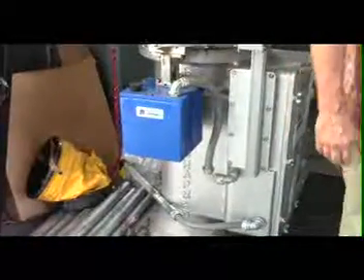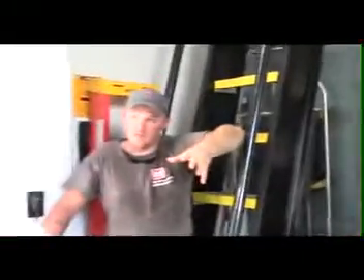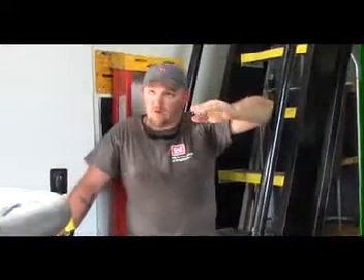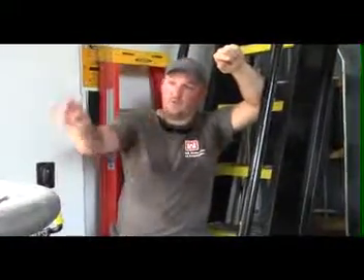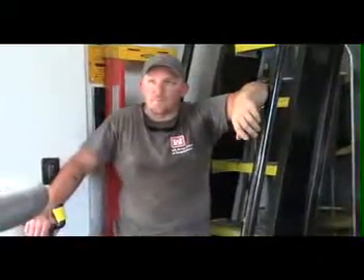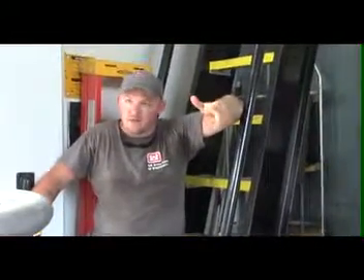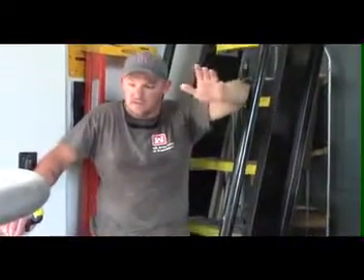Are you familiar? You know what a megger test is? Test the breakdown of the insulation in the windings. We had 1 motor out of 6 that the numbers were starting to fall off. So we've been rebuilding 2 motors a year. Do you redo the winding? Yes, they rewind the motors, new bushings, bearings, seals, test everything.